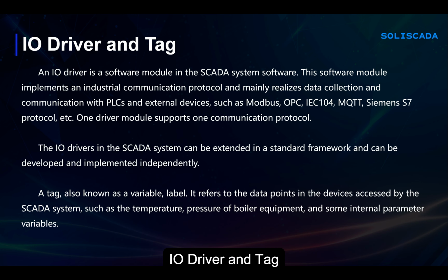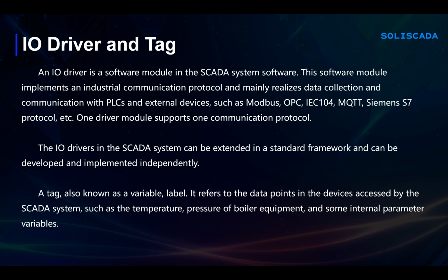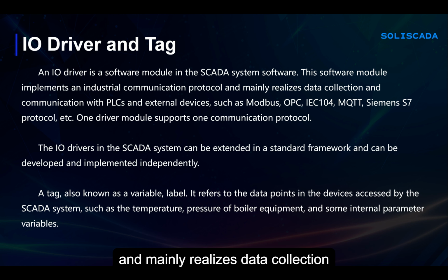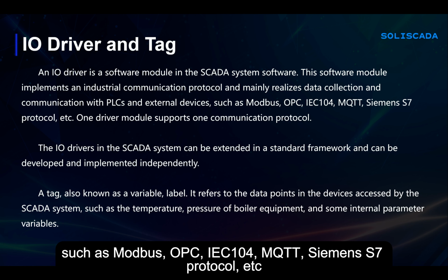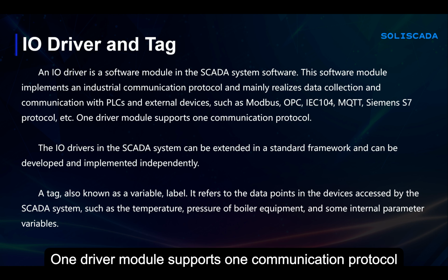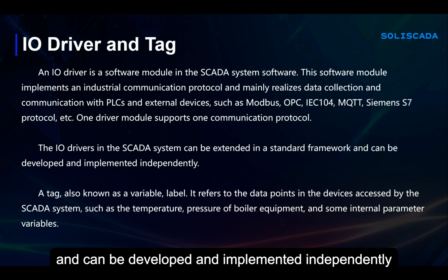I/O driver and tag. An I/O driver is a software module in the SCADA system software. This software module implements an industrial communication protocol and mainly realizes data collection and communication with PLCs and external devices, such as Modbus, OPC, IEC 104, MQTT, Siemens S7 protocol, etc. One driver module supports one communication protocol. The I/O drivers in the SCADA system can be extended in a standard framework and can be developed and implemented independently.